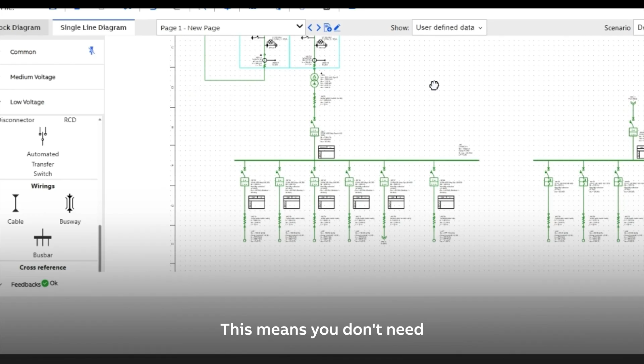Let's say we set this load factor to 80%, or 0.8. If we change the loading factor to 0.8 and run the calculation, what happens? This feedback is now cleared. This means you don't need to change the transformer size, and all your loads are normal. We can use a loading factor of 80% here, which is fine. The diversity factor is actually the same thing.